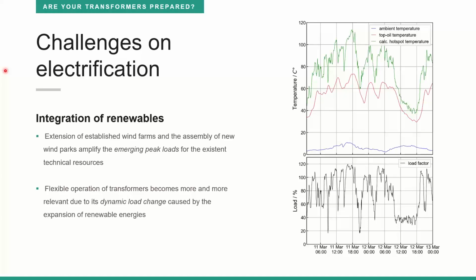In this figure, you can see the loading of a wind farm transformer over 2 days. The lower black curve shows this loading. You can see that during this 2-day interval, we have quite high loads of 120% on these transformers. We also have quite strong changes of the load, so a quite strong dynamic loading. Here we have a decrease from 100% to almost 0 and back to 100% in a very short time. So the new operation scheme of these transformers is characterized by emerging peak loads and quite high dynamic load changes.